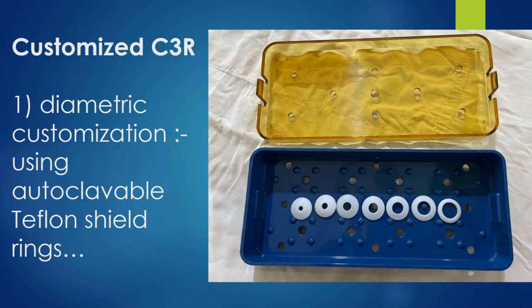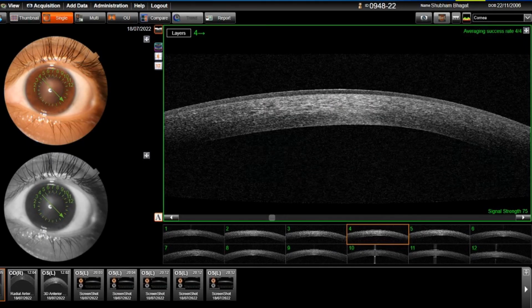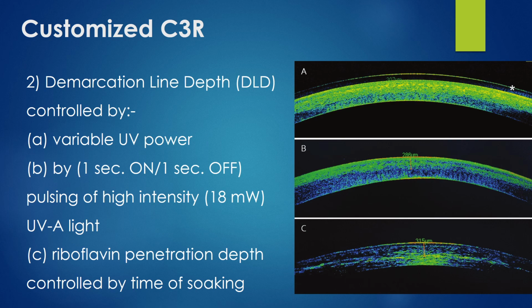Diametric customization of dosing can be done using autoclavable Teflon shield rings, which are changed at every 3 or 4 minutes interval during the procedure. Excellent result of customized C3R done by Uvglo. Demarcation line depth can be controlled by a variable UV power or by 1 second on 1 second off pulsing of high intensity 18 milliwatt UV light, or by riboflavin penetration depth controlled by time of soaking.